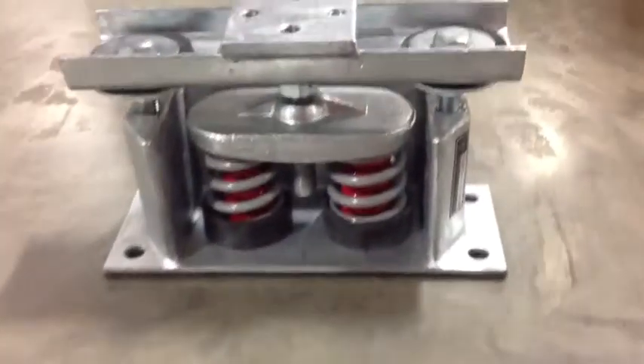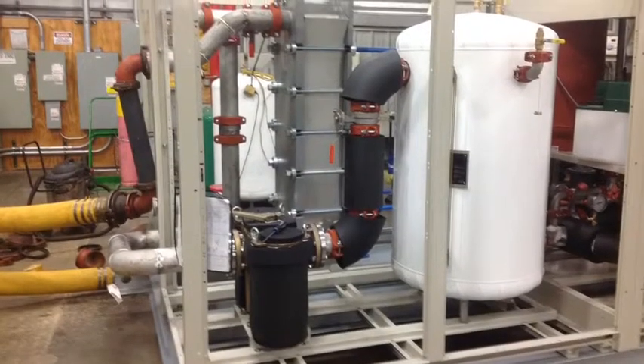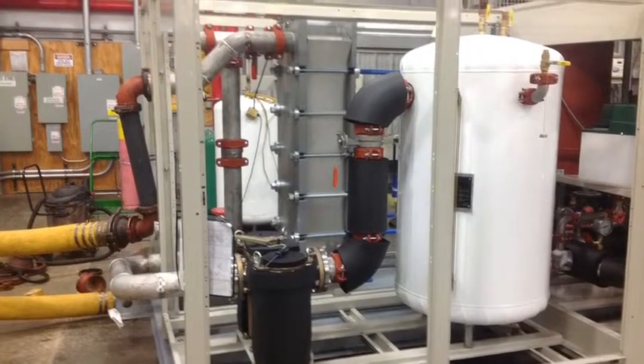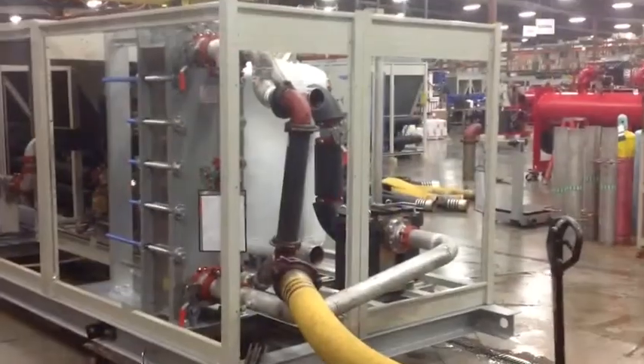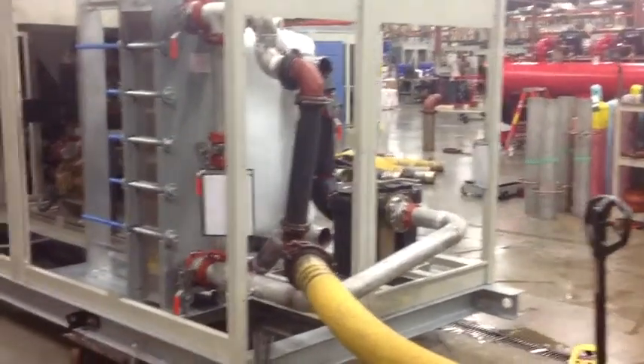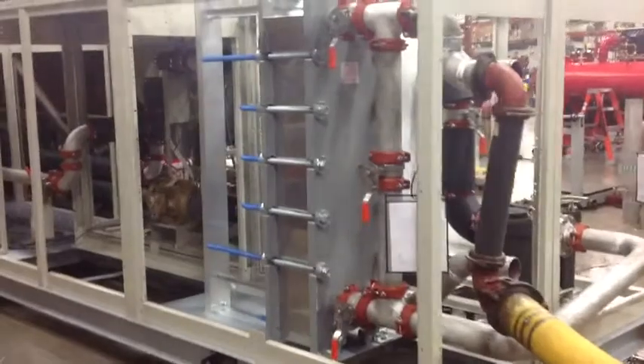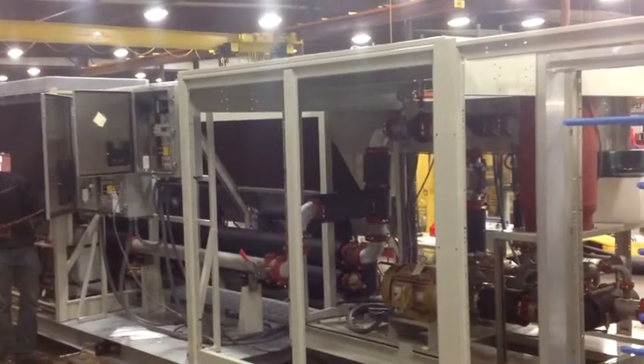In this next view, you see the seismic isolator with the 4 holes in the top. Only one of those is used to connect to the chiller lifting frame. The holes in the base plate are used to connect to steel dunnage. This is a view showing the heat exchanger in the background of the storage tank. We've now panned around and are looking again at the heat exchanger, which decouples the building comfort cooling loop from the space being served by this chiller.